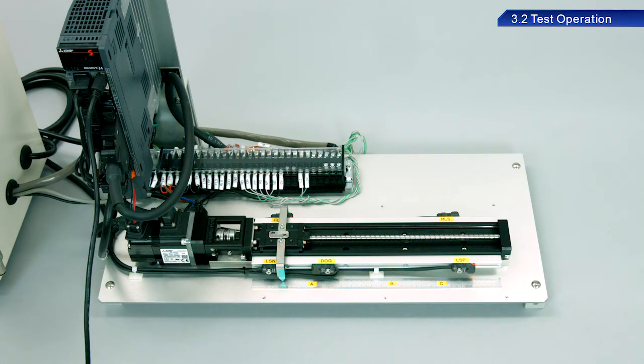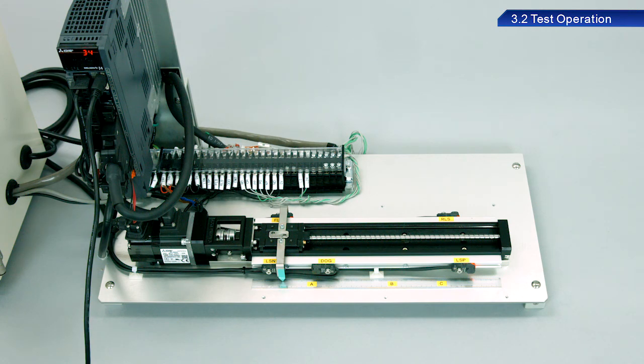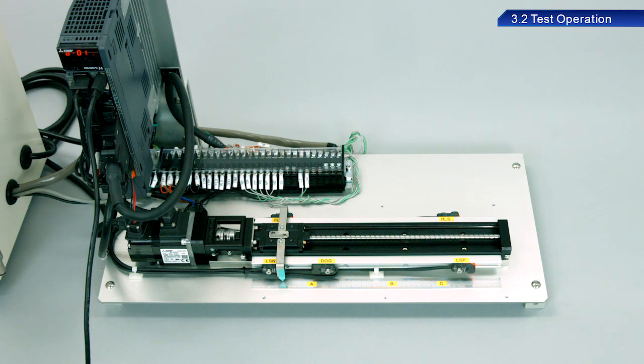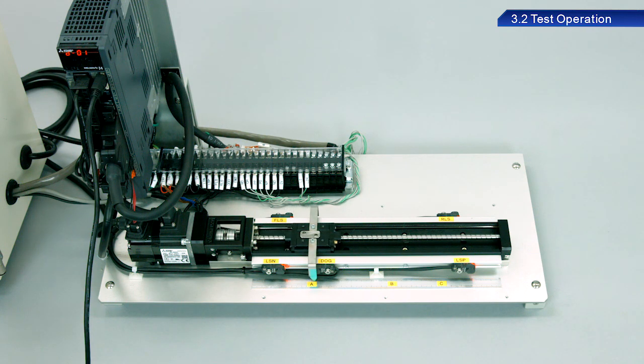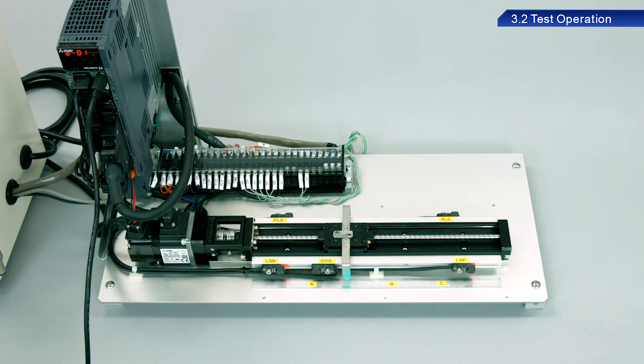Turn the power off and on again. The alarm is cleared by turning the power off and on. Then move the motor in the opposite direction of that before the servo amplifier stopped. The motor should have moved again.